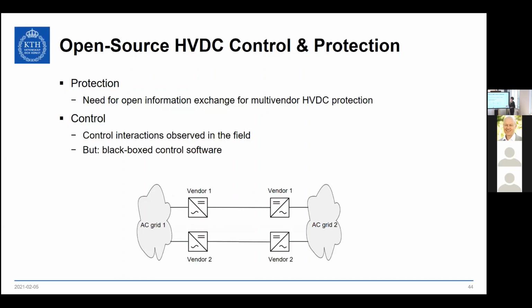You might argue: then build one link with purely one vendor, who knows everything going on, so you can control and tune the control and protection exactly as needed, and it works. Another vendor can do the same, with no need to make the control open. But if they are electrically close on the AC side, there's still potential for unwanted interactions, and then we're back to how you solve that if you can't investigate the problem because the control is black box, and how you modify it in a multi-vendor setup. The same story applies if at some point they connect on the DC side.